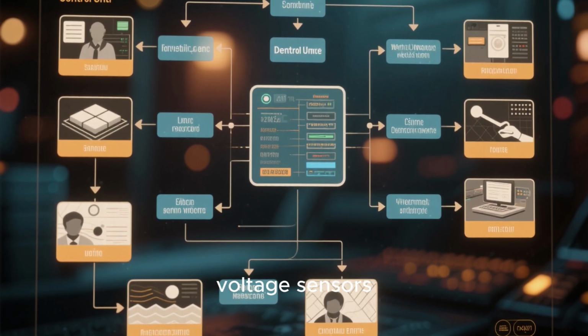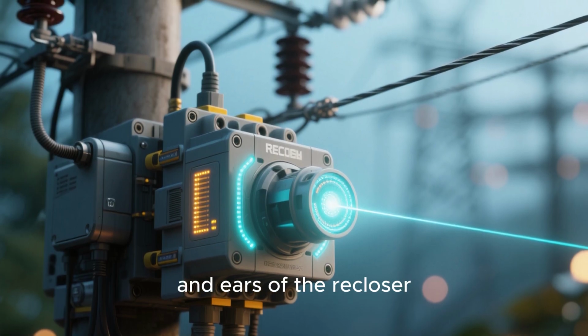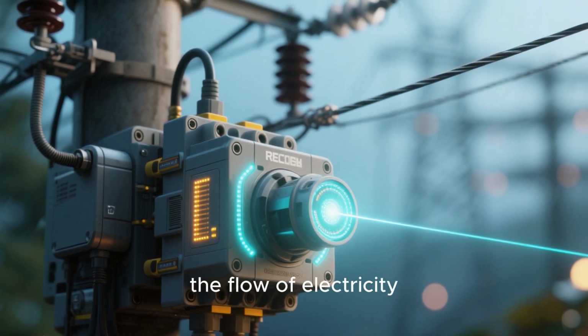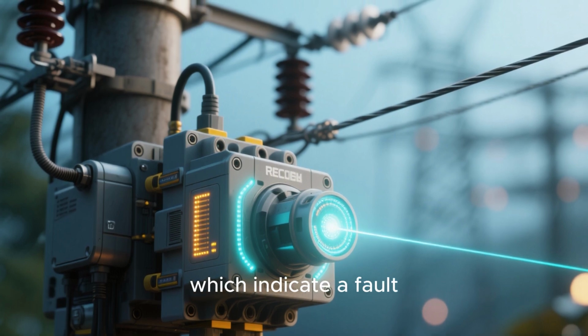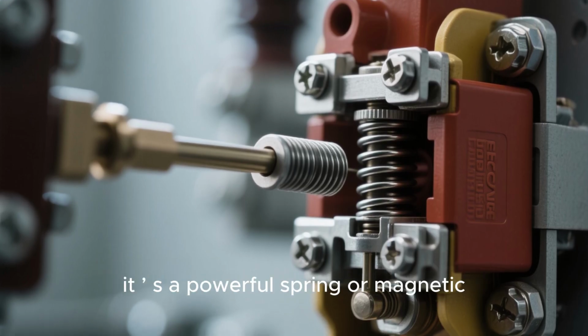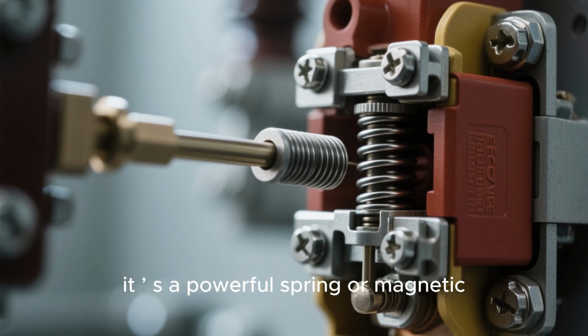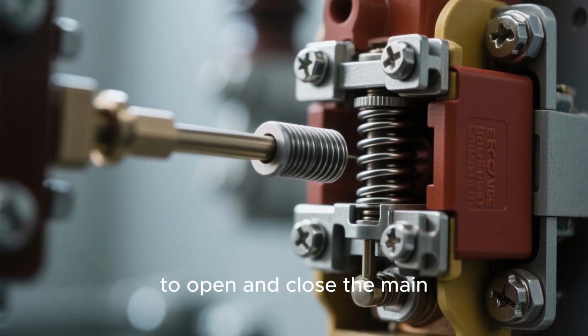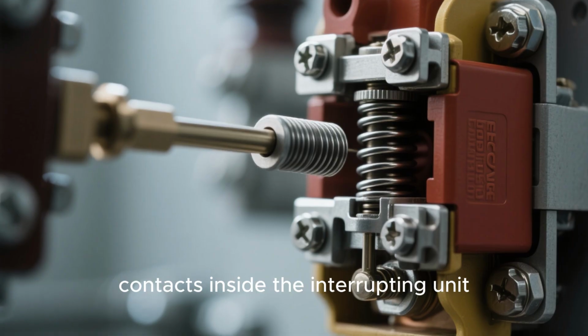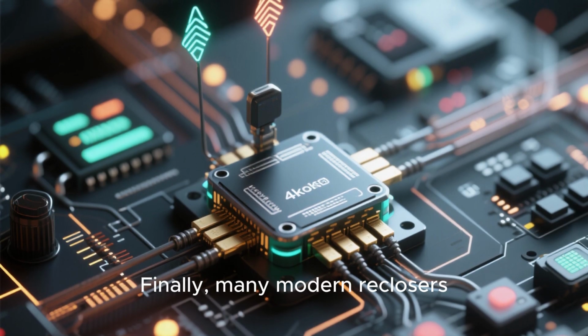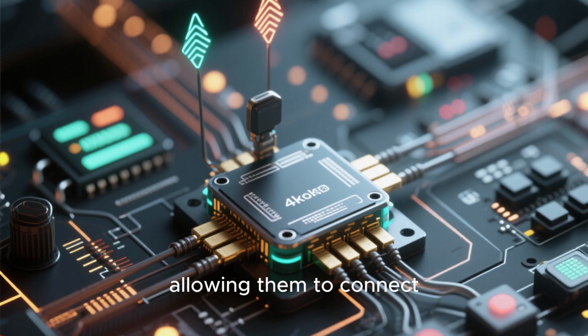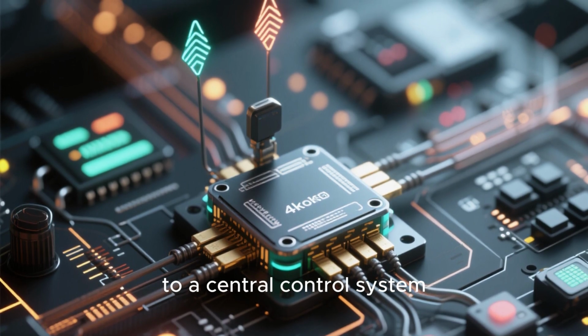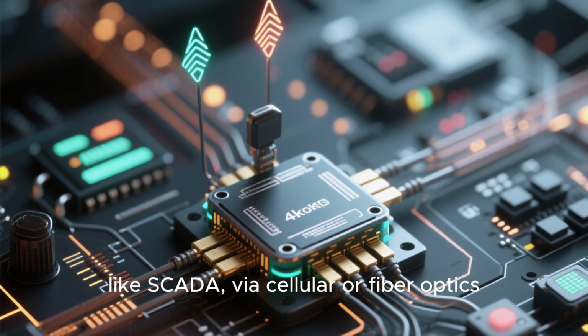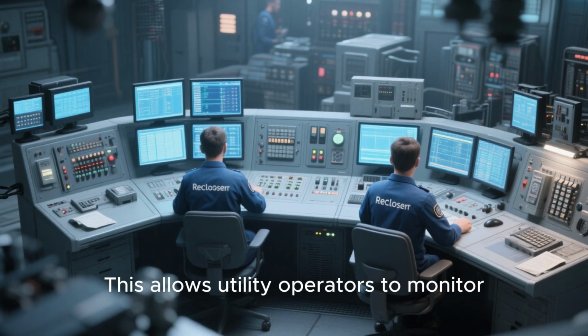Next are the current and voltage sensors. These are the eyes and ears of the recloser, constantly monitoring the flow of electricity to detect abnormal conditions like overcurrents, which indicate a fault. The operating mechanism is the muscle. It has a powerful spring or magnetic actuator that provides the force needed to open and close the main contacts inside the interrupting unit. Finally, many modern reclosers have a communication module, allowing them to connect to a central control system, like SCADA, via cellular or fiber optics. This allows utility operators to monitor the device and even control it remotely.